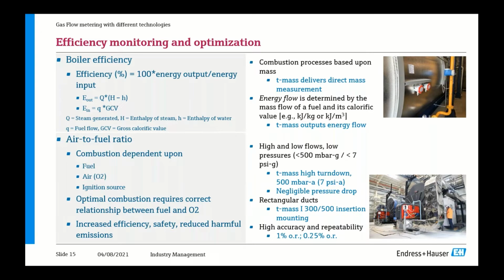Also very important to the combustion process is the air to fuel ratio. Getting this relationship correct, making sure the mixture between air and fuel is correct, is very important because that has a large influence, of course, on the efficiency of the combustion and in the end also on the boiler efficiency. It also has a very large impact on the amount of harmful emissions that are released into the atmosphere. And that can also be manipulated by getting the air to fuel mix correct.